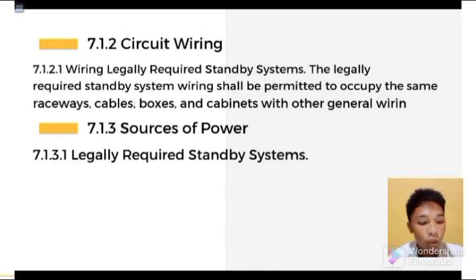Third type is the dual fuel supply. Prime movers shall not be solely dependent on a public utility gas system for their fuel supply or municipal water supply for their cooling systems. Means shall be provided for automatically transferring from one fuel supply to another where dual fuel supplies are used.